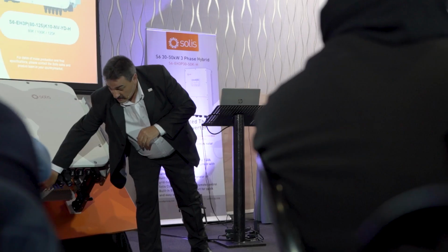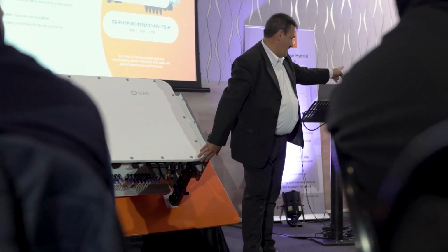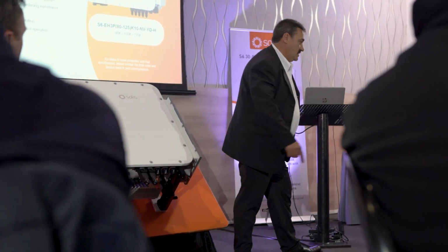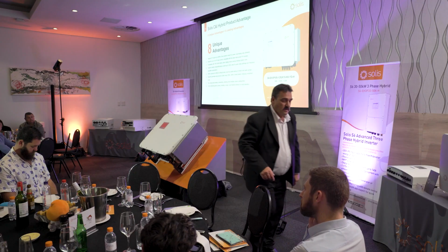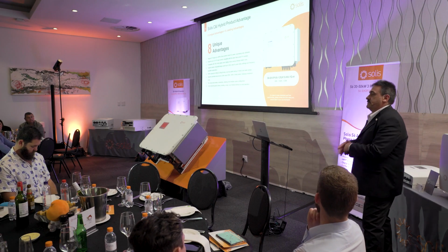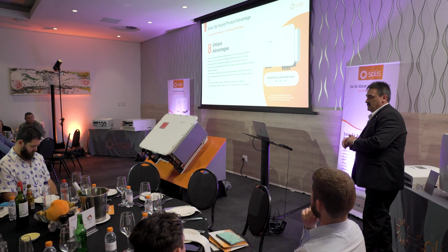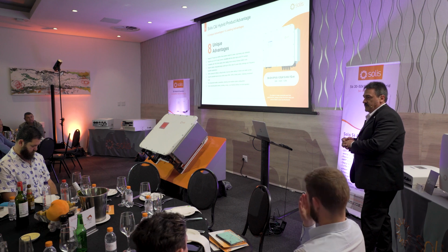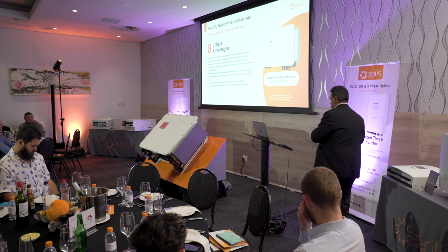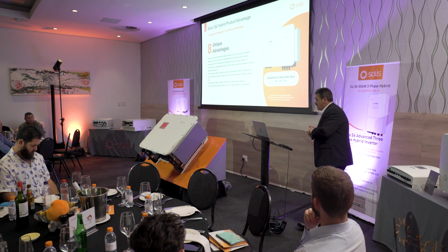Okay? So to give you an idea, this inverter boasts the same amount of MPPTs as that. So it's 10 MPPTs with 20 strings going in at 21 amps a string. So 42 amps per MPPT. Okay, with 1,000 volt open circuit voltage on the PV side. So it's quite powerful.